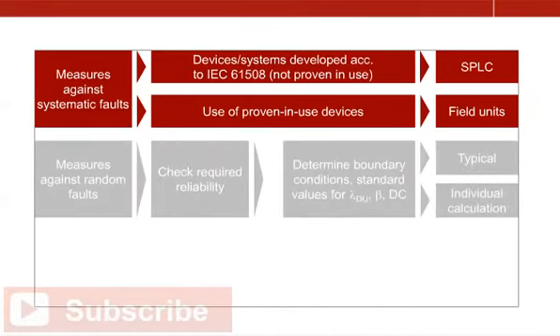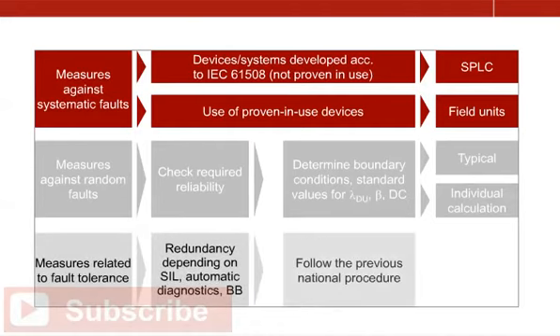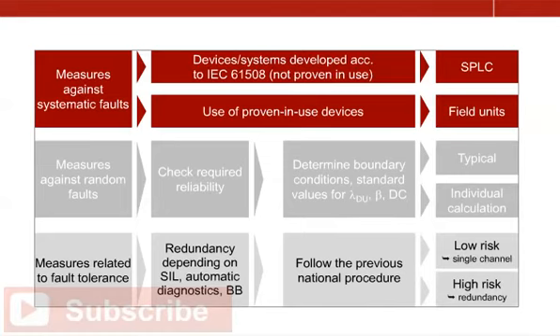For random faults, it is necessary to start by determining the required probability of failure for a certain safety integrity level and verify that it is actually reached based on failure-related parameters provided by the manufacturer. For guide values of typical field units referred to VDI VDE 2180. Fault tolerance is guaranteed by redundancy. It depends on the existing risk whether a single-channel version is sufficient or not. Further measures are added in the form of automatic diagnostic functions.